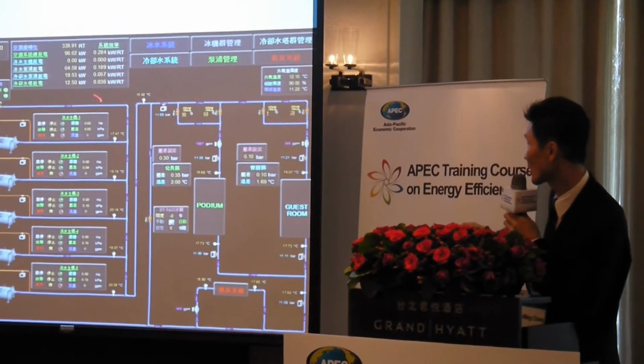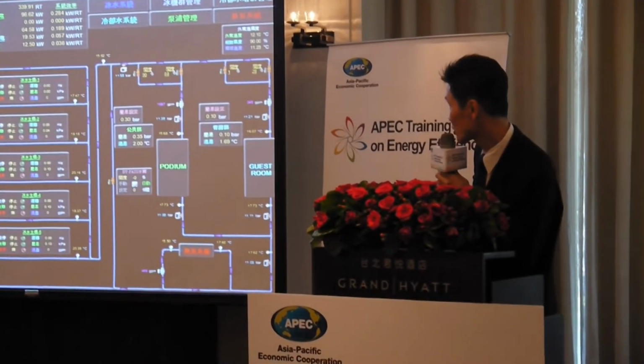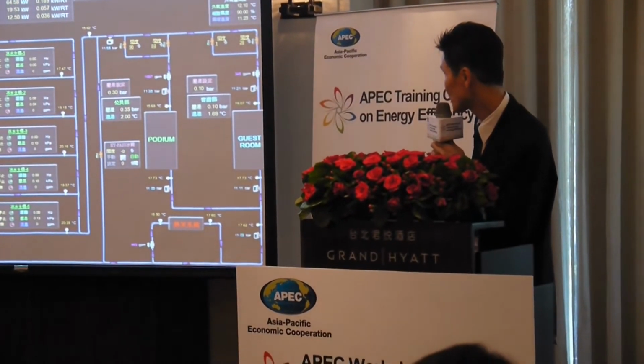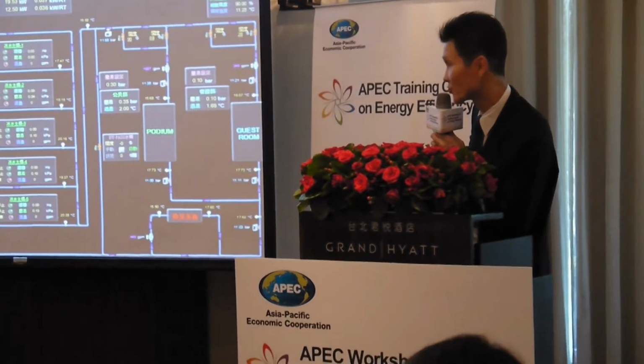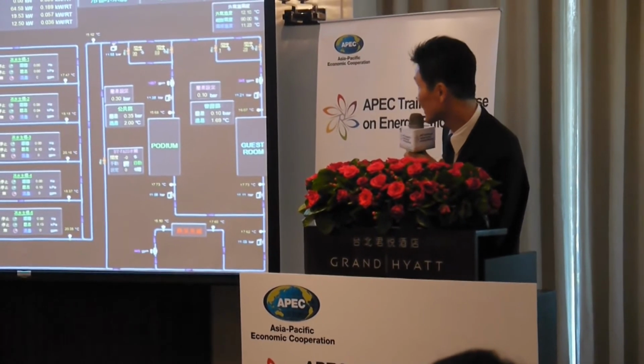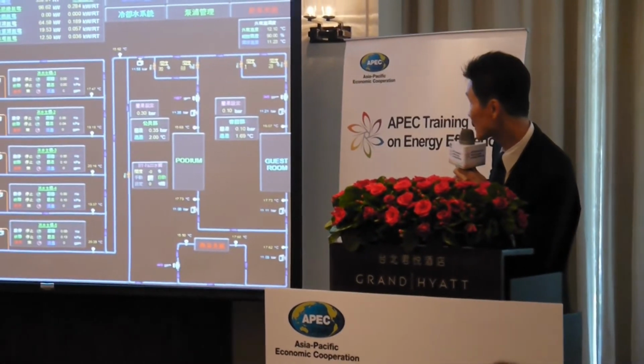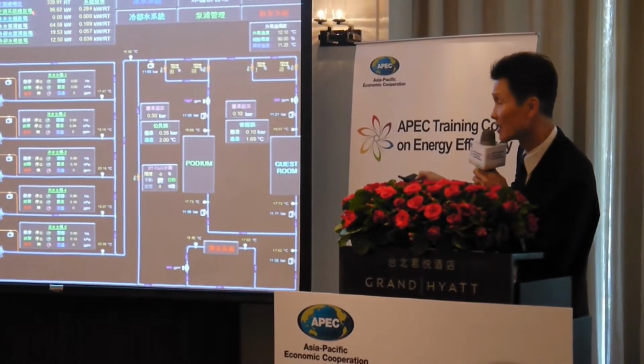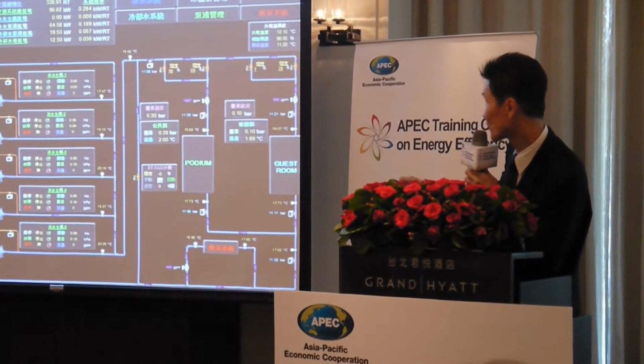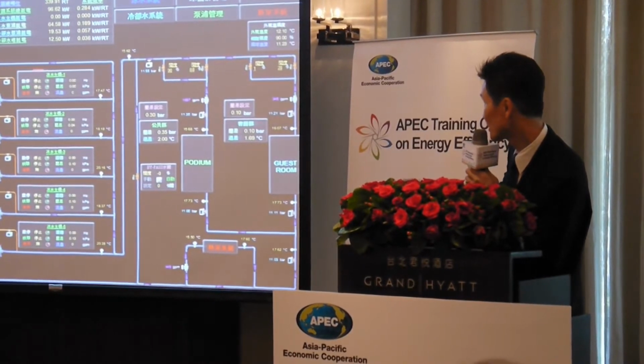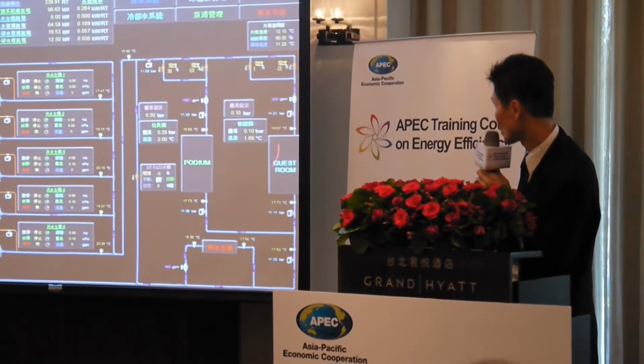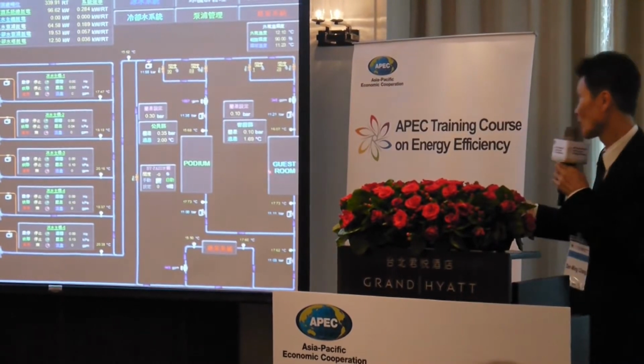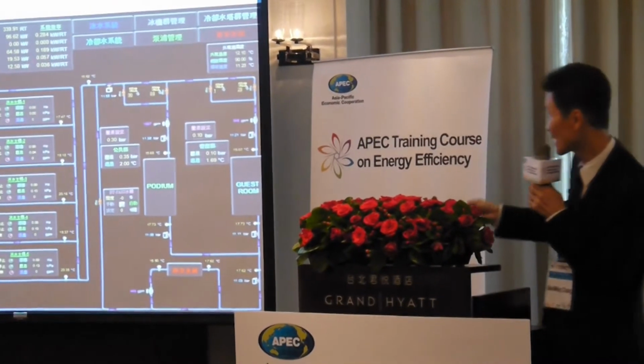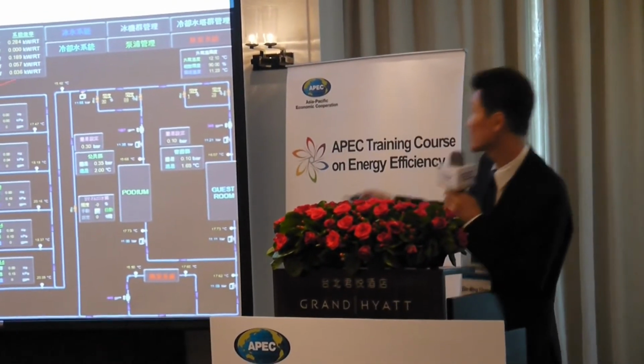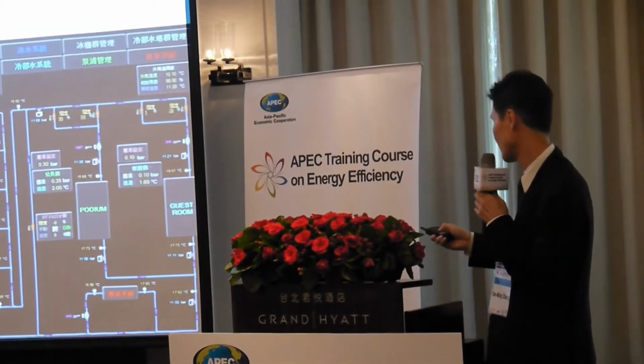Where does it come from? It comes from here. The chilled water will not go through the chiller, we go to the heat exchanger. The other side, later I will explain, goes to the cooling tower. That means cooling tower water comes from here to the heat exchanger and produces chilled water here and supplies the system. So we can get the most saving. Without starting the chiller, we still have chilled water to supply in the winter time.